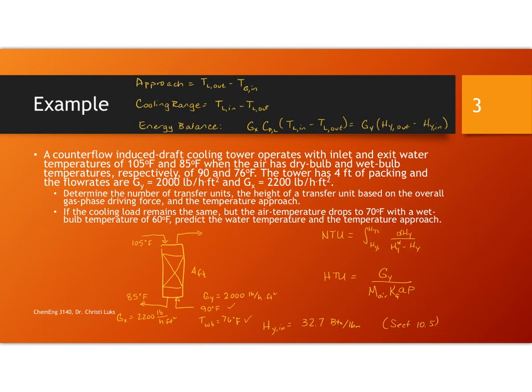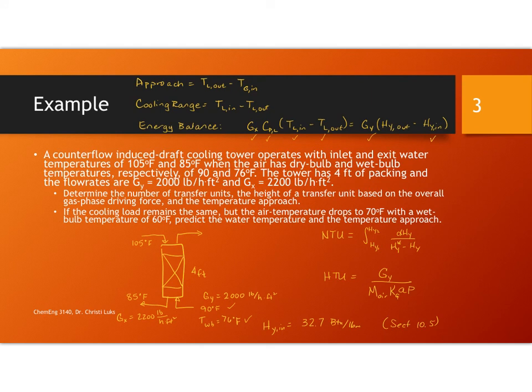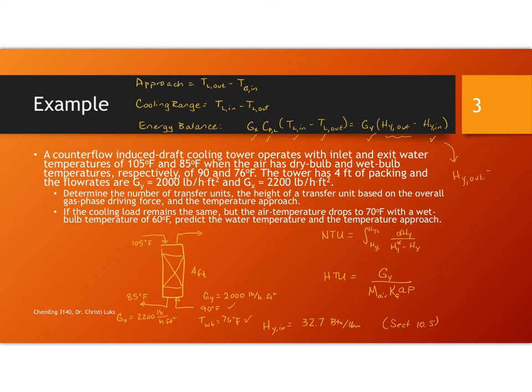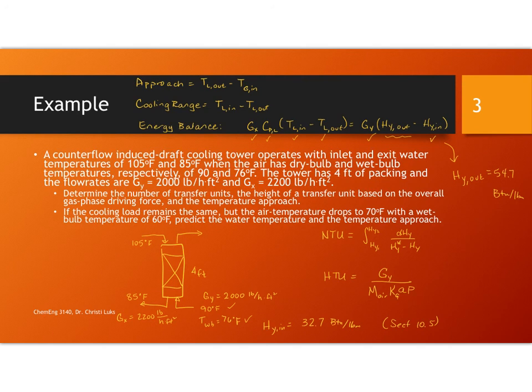In my energy balance I know the enthalpy coming in, I know G sub Y, I know G sub X. The liquid is water so therefore I can find C sub P. I know the temperatures at the inlet and the outlet. So I can use this to solve for HY at the outlet. 54.7 BTUs per pound of dry air is my exit enthalpy for this gas.